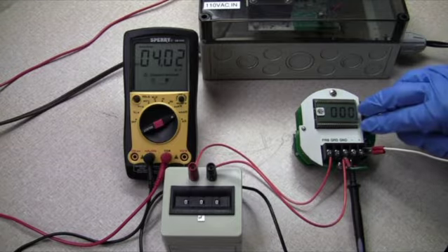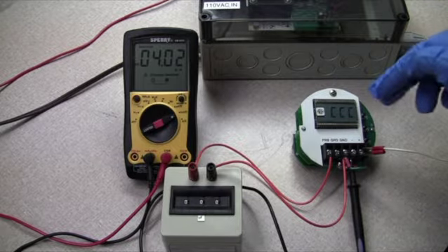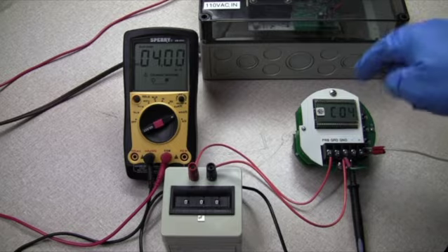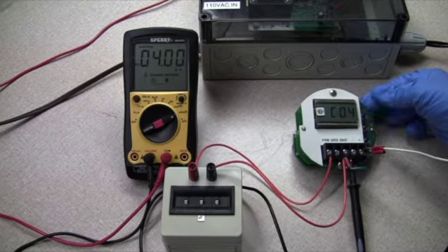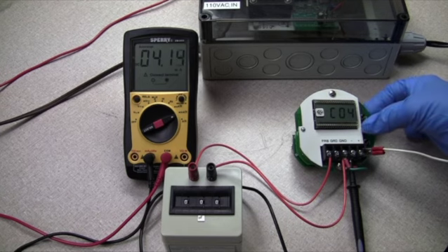What we're going to do is hit SW1 and SW2 at the same time. Three C's will pop up, and SW3. This is calibration mode. We're setting our 4 milliamp. So as you can see, if I push the SW1 button, I can toggle it upward, and the SW2 button, I can toggle it downward.